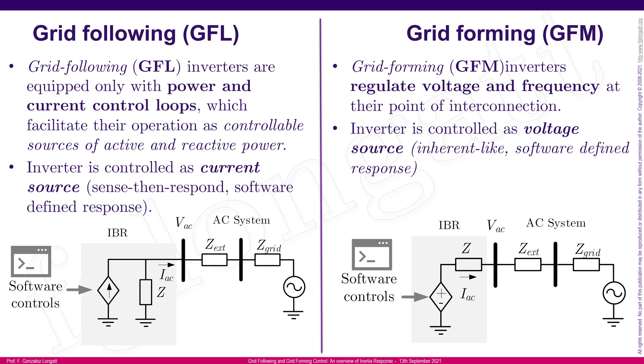When mimicking inertia response, inverter-based resources are grouped into two broad categories: grid following converters and grid forming converters. The grid following converter has been in the market for many years. It uses additional control loops for current control and active power, controlling the converter via the classical dq-axis, modeling it as a current source — typically used for PV systems but applicable to other sources.